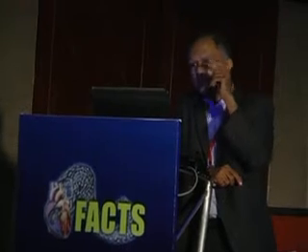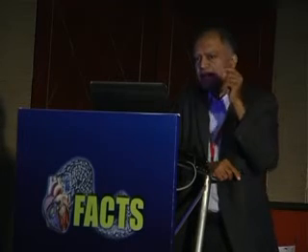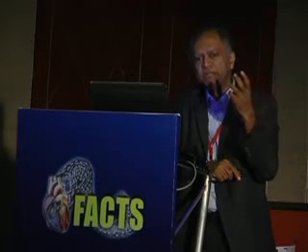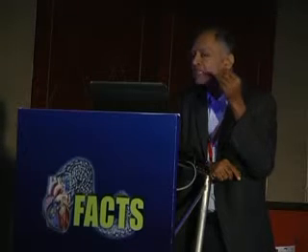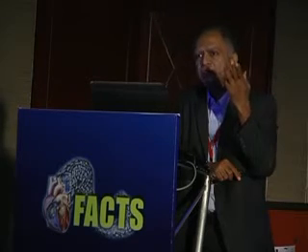And the single most important thing is, Dr. JP did emphasize this, when you implant a lead, the measured R wave tells you whether you are in a scarred area or whether you are in a healthy area. You put an LV lead and you get an R wave measurement of 9 or 10, it's a good healthy area. Whereas if you put it in a circumflex scar, you are unlikely to get a very good R wave.